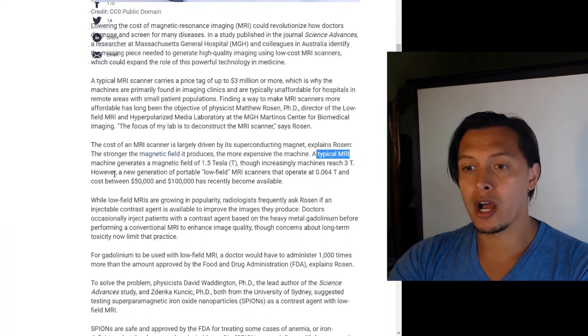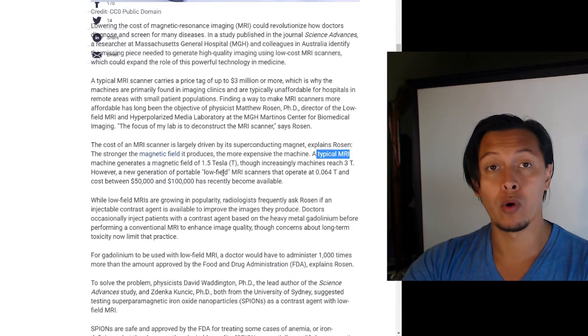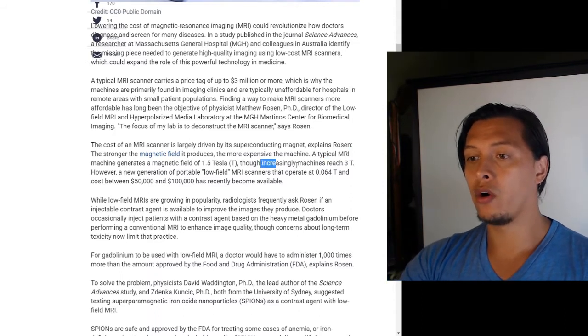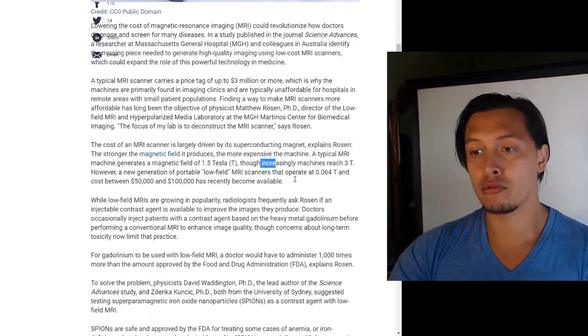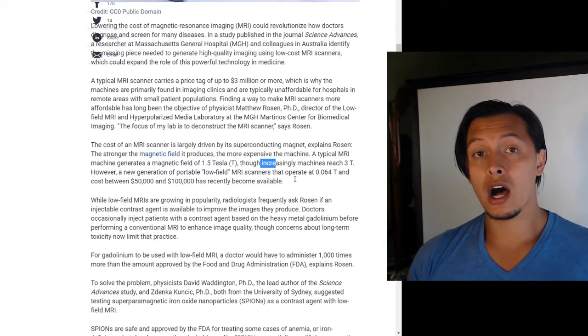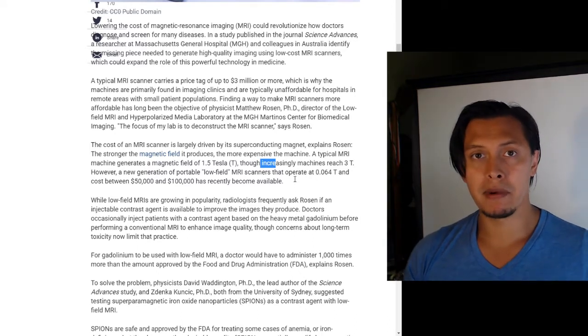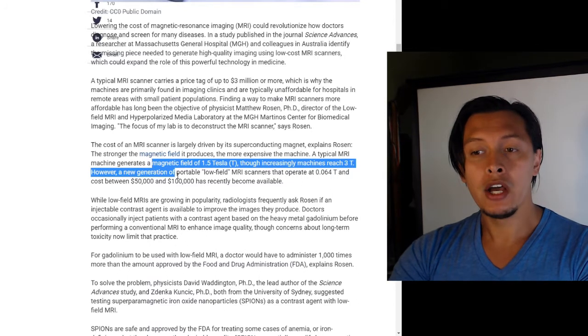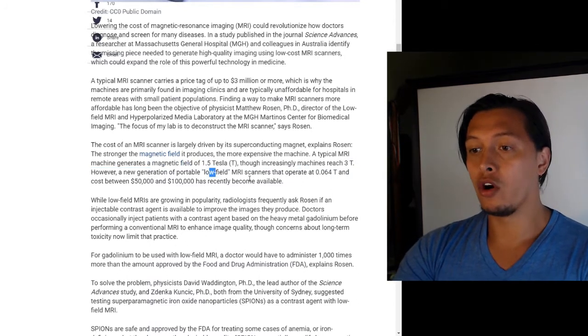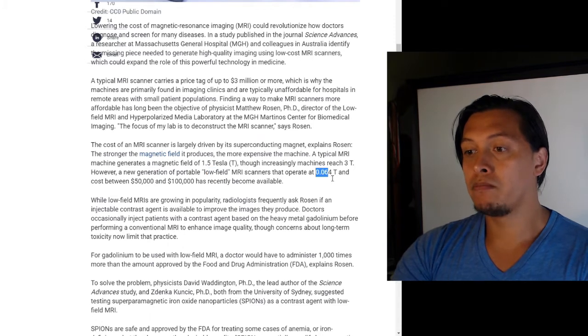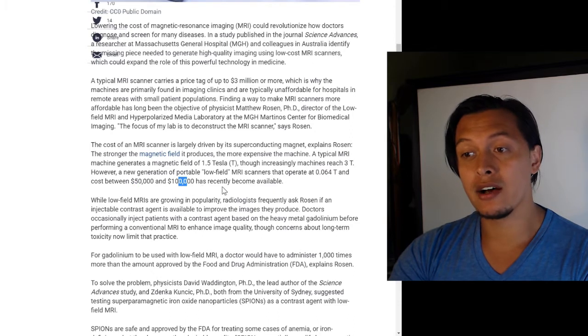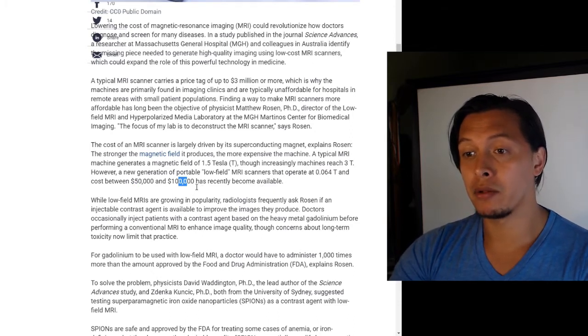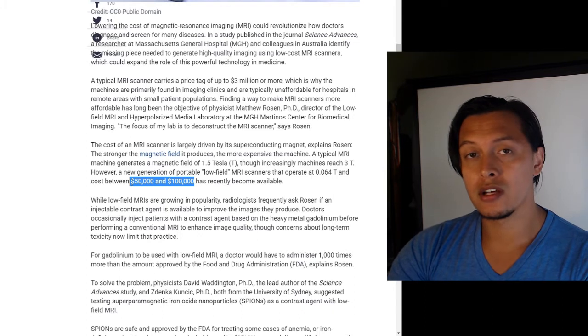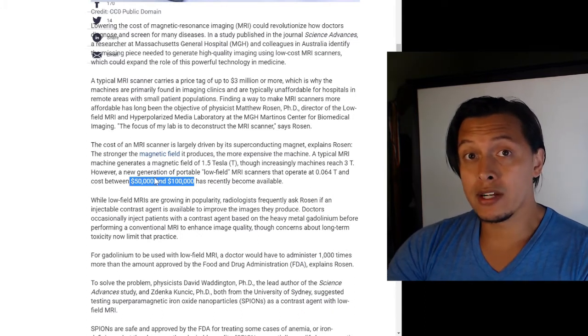A typical MRI machine generates a magnetic field of 1.5 Teslas, though increasingly machines reach 3 Teslas. Tesla is a measurement of the magnetic field strength at a location. However, a new generation of portable low-field MRI scanners that operate at 0.064 Tesla and cost between $50,000 and $100,000 has recently become available. So, $50,000 to $100,000. This is within the price range that many hospitals can afford.